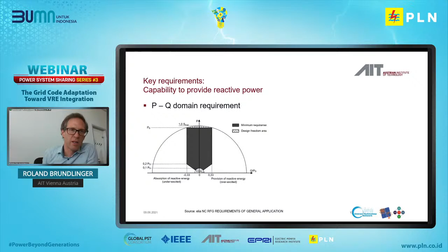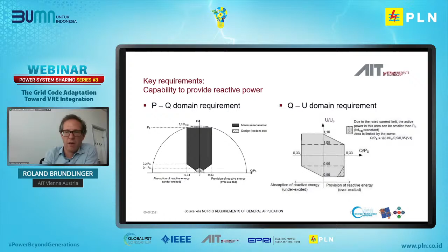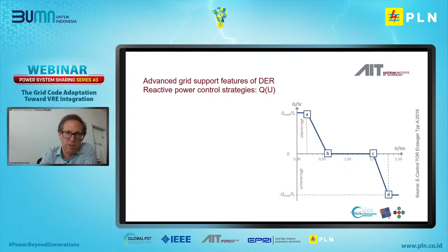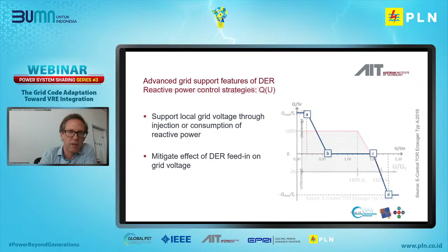Then we already heard a little bit about reactive power capabilities. So this is also a requirement which is today in place in most European national grid codes, and it's defined in different ways. So we have a requirement in the PQ domain, and we also have a requirement that the reactive power needs to be provided in a defined voltage range. And what to do with the reactive power, how to utilize these reactive power capabilities? So there are different control strategies, and one control strategy which seems to be most promising today is the Q of U. So basically a reactive power as a function of the grid voltage control to support the local grid voltage through the injection or consumption of reactive power, and of course to mitigate the effects of the feed-in on the grid voltage.